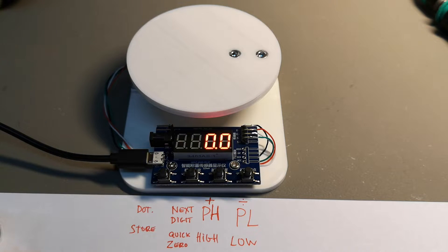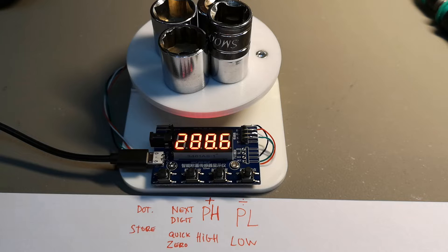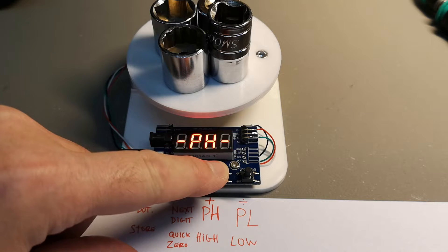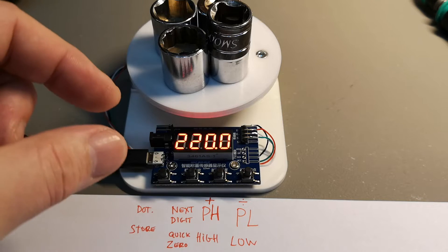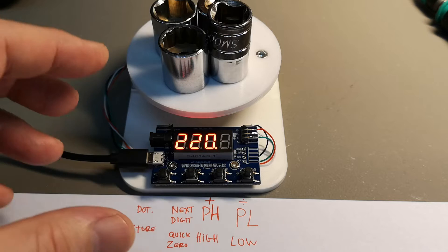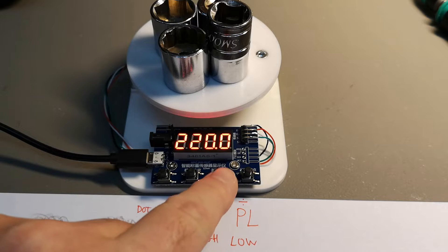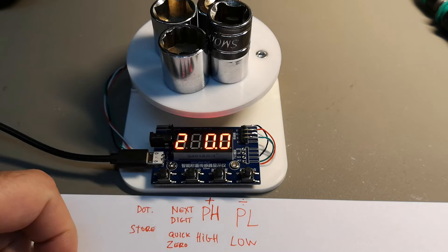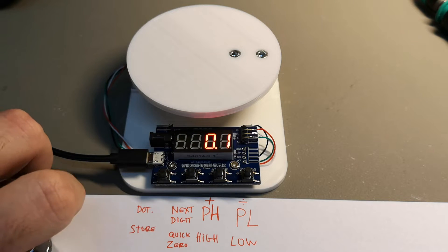It blinks to show you that you have zero stored, so now it goes from zero. For the high setting, use something you know the exact weight of — I know these four pieces of metal are exactly 220 grams. Place them on the scale, hold down PH for a few seconds. It conveniently remembers the last value you input when storing the high value, which is very smart for repeated calibrations. Set it to 220 and store it.